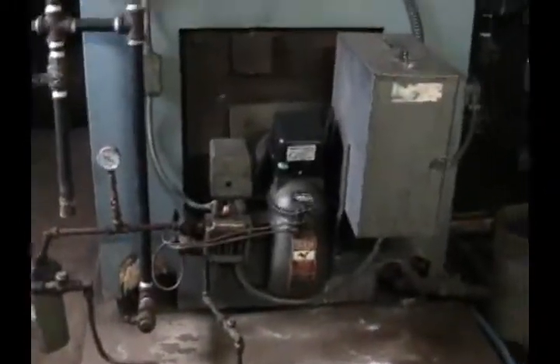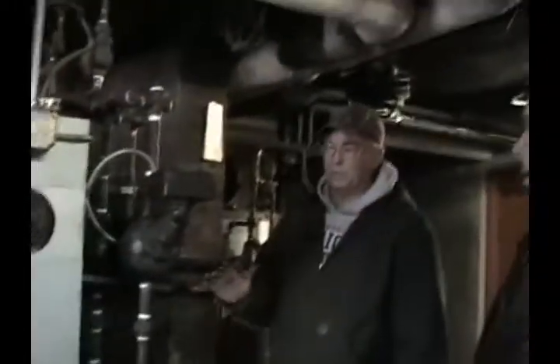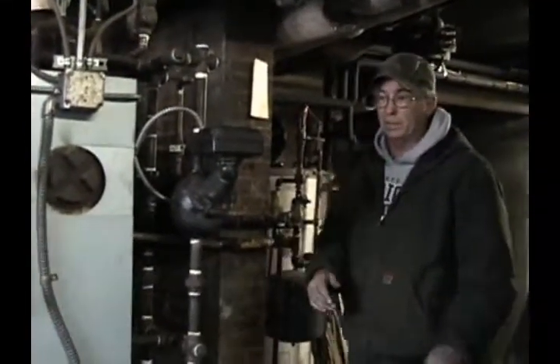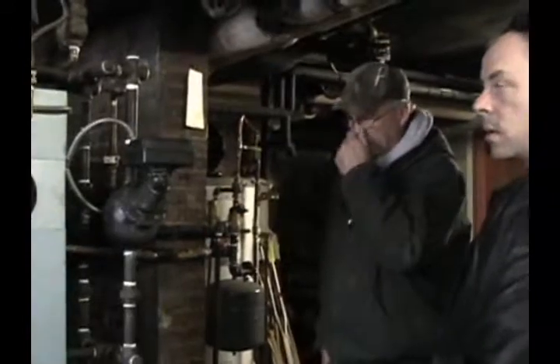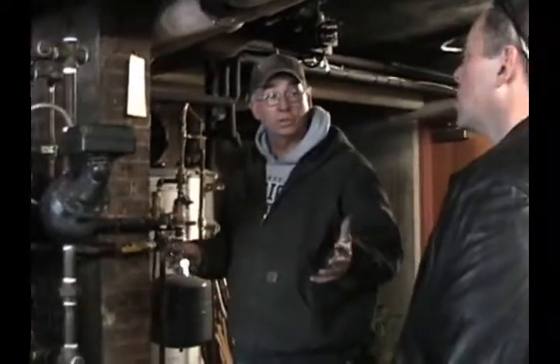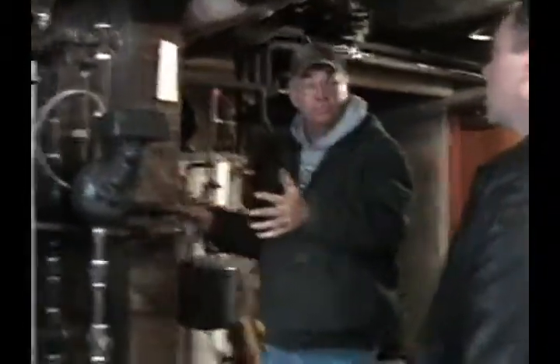Now, is this something that's going to remain and just switch the burner out to gas? I would not. No. First of all, you don't want to go with steam. Steam, you have to boil water to make heat. You're pushing it to 220 degrees. This is just a big pile of scrap metal, basically. Right. And, I mean, this you could almost put the wall-hung boilers, you could almost do them in each room.